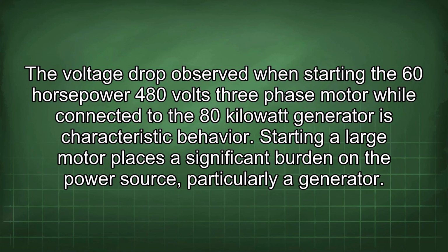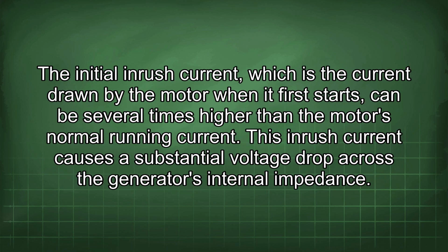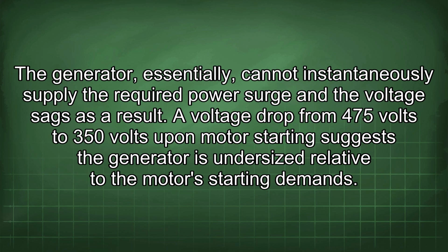The voltage drop observed when starting the 60 horsepower 480 volts three-phase motor while connected to the 80 kilowatt generator is characteristic behavior. Starting a large motor places a significant burden on the power source, particularly a generator. The initial inrush current, which is the current drawn by the motor when it first starts, can be several times higher than the motor's normal running current. This inrush current causes a substantial voltage drop across the generator's internal impedance. The generator essentially cannot instantaneously supply the required power surge and the voltage sags as a result.